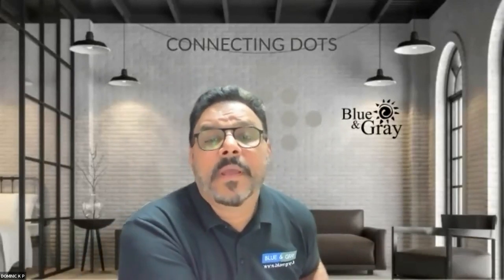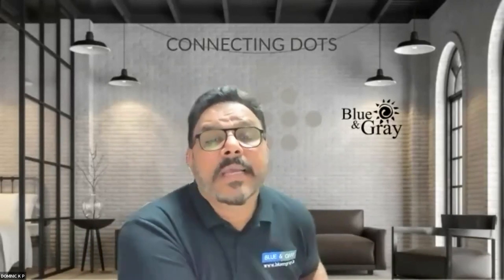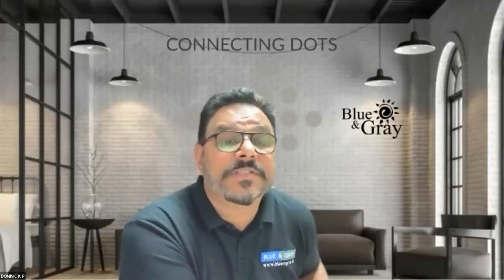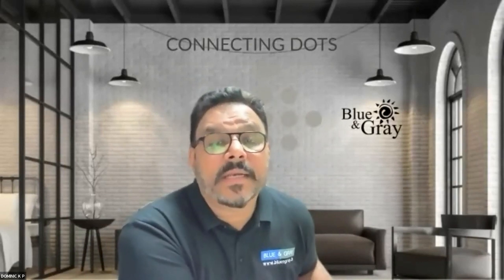Okay, moving to Nitin's second question, which I also felt is good. There is a device called an electrical safety analyzer. However, according to NABH, calibration by a third-party company is called calibration, which is a wrong practice. Not a single MNC such as GE, Siemens, Philips practices using an electrical safety analyzer. They check with a multimeter and close the PPM saying electrical safety test done. Even the PPM checklist is filled in later instead of during the checking of the machine. I think it is suggesting, why do they practice it outside India, and why is it not being practiced in India?